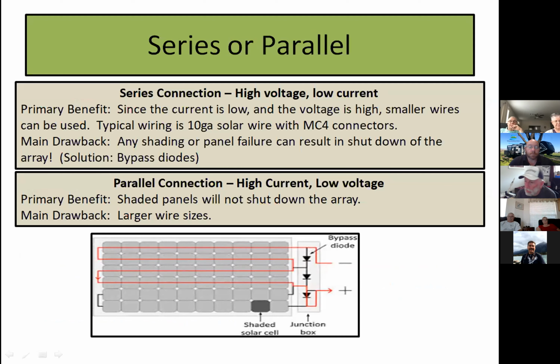Now in this chart, it talks about whether you want to run your panels in series or in parallel. When solar first came out, running panels in series gave you nice high voltage and low current, allowing smaller wire sizes. But the problem was if you got shaded on any one panel or portion of a panel, you would lose the entire charging configuration. So all panels pretty much went into a parallel configuration years ago.